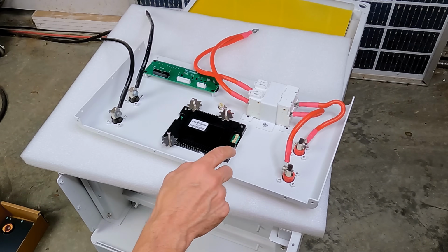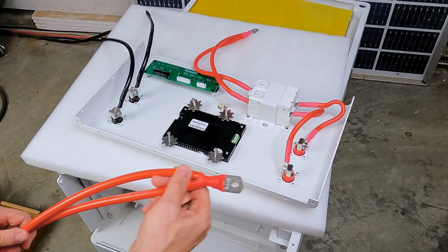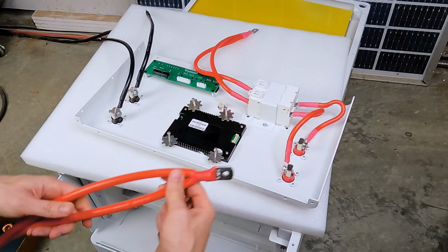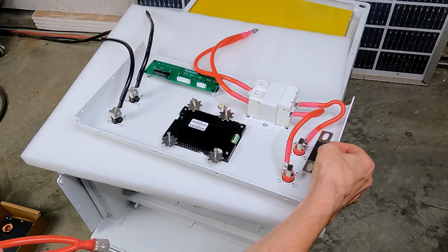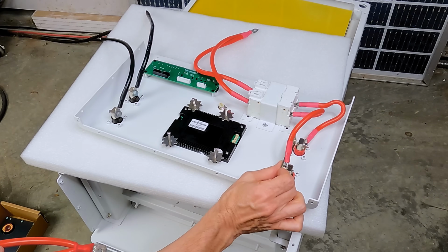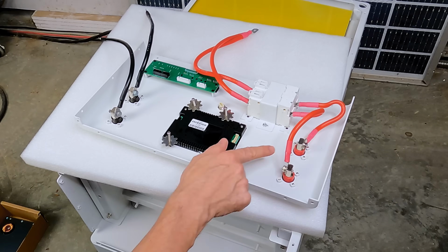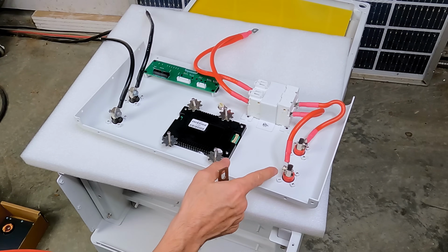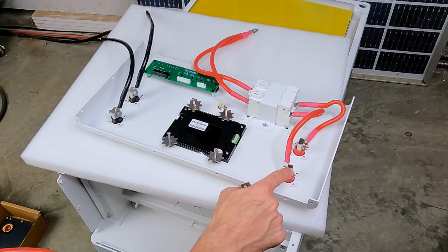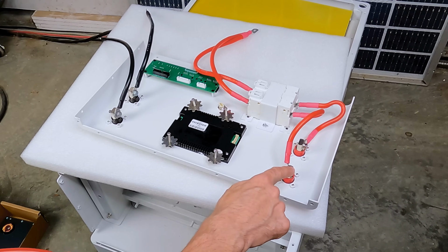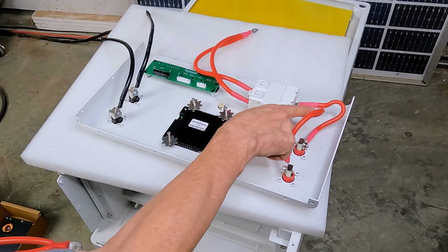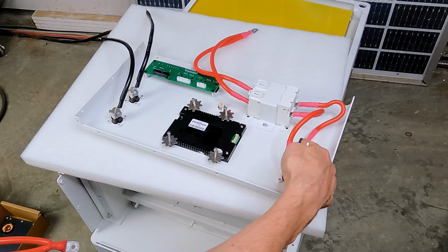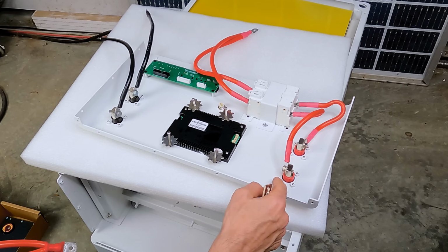In order to get 170 amps out of this, we need two 4-gauge cables and a bus bar connecting these two lugs together. You can't have these on separate wires, because if you connect your load or source to one of these posts, all of the energy goes through one cable and has to circle back out through the other to the next battery.